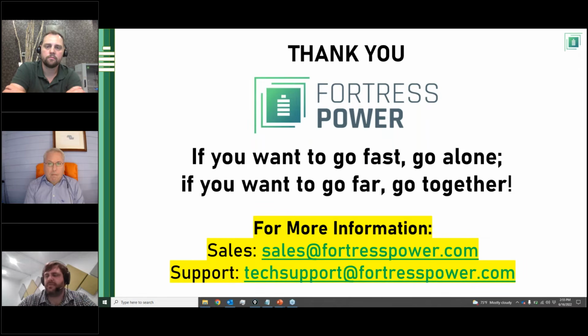We have found not too many inverters actually allow you to program all the settings in voltage mode that you would want for lithium, whereas programming by percentage is more user friendly. Also, the inverter voltage is not the same as the internal voltage of the battery. There's usually a significant discrepancy between the perceived voltage of the system and the actual internal voltage of the battery.